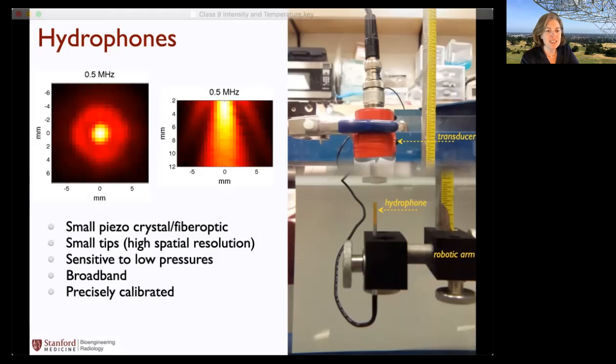So a hydrophone is essentially a small piezoelectric crystal, or it could be a fiber optic sensor. It is set up in a scan tank, as shown over here on the right. Here's a hydrophone. It's a very small hydrophone here inside the water bath. And then there's a transducer up above. Typically, the ultrasound will be set up to send small pulses out periodically, and the hydrophone will measure them. It's on a robotic arm, and it's going to be moved around and make multiple measurements. So it looks something like this.